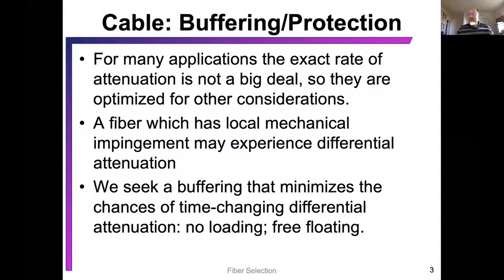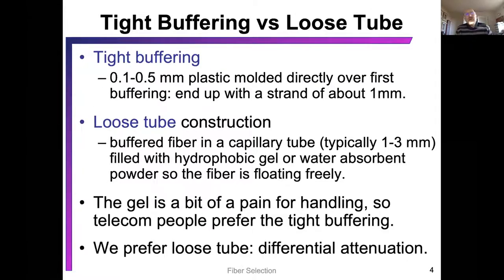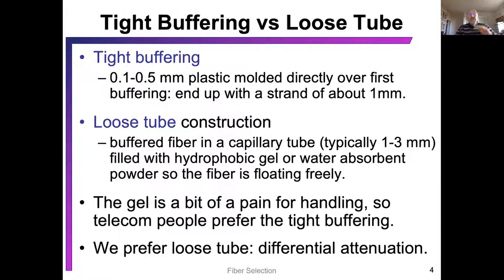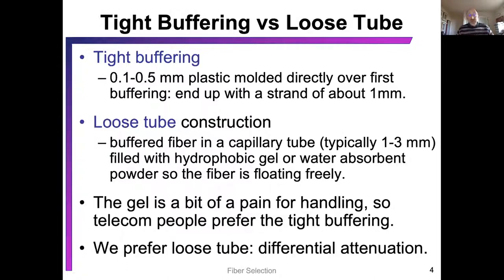We go to our cable manufacturers and ask for really well-protected cable. You'll hear two terms: tight buffering and loose buffering, or loose tube. Tight buffering is when they inject the plastic jacket over the fiber with no airspace, so there is a mechanical connection between the exterior and the glass itself. Tight buffering is often used in telecommunications, where they don't care about signal amplitude — only ones and zeros. We have a much higher need for quality of signal; a 1% change in signal level is disastrous for us. So watch out for cables that are fine for telecom but not for DTS.